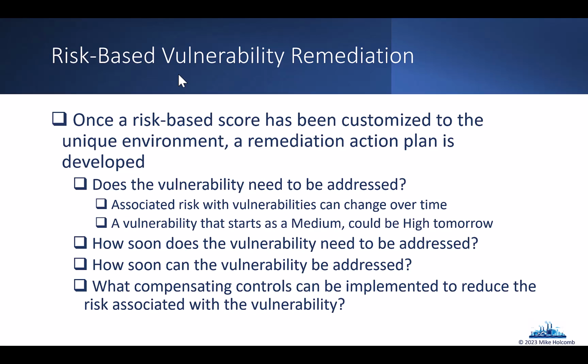An example I always go back to, and we talked about it previously in the course, is the Trisis incident. One of the big issues with the Trisis incident was that the SIS, their fail-safe backup controllers, were not segmented from the rest of the network. So what if we found that the SIS not only had keys in program mode and used default passwords, and maybe had a critical risk vulnerability, but we couldn't take those controllers offline without taking the plant offline, and we couldn't do that for the next 9 months.